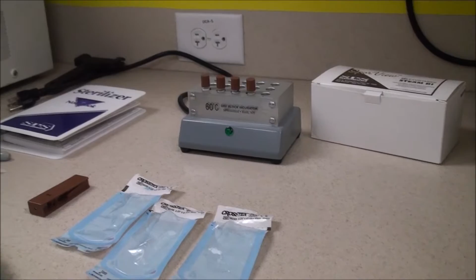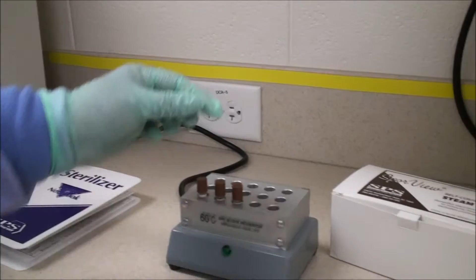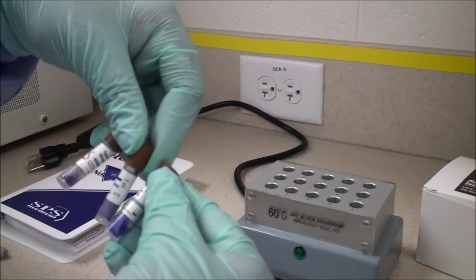To read the spore test, the control should turn yellow. This means that it is positive. The capsules that have been run through the sterilizer should not turn yellow. They should be purple or brownish in color, indicating a negative test result. Make sure the information is recorded on the log sheet at the end of this section. Remember to check each capsule after 24 hours.